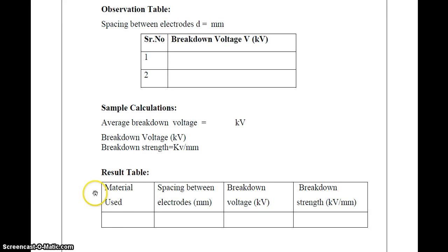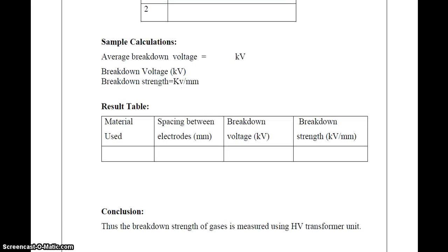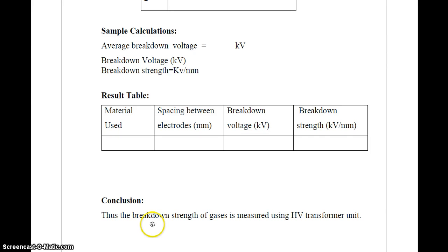Then finally the result table: which type of material, such as gaseous material like air. Then the spacing between the two electrodes, denoted as d in mm. Then breakdown voltage in kilovolts. Then breakdown strength in kilovolts per mm. Okay. Then finally the conclusion: thus the breakdown strength of gases is measured using the high voltage transformer kit.